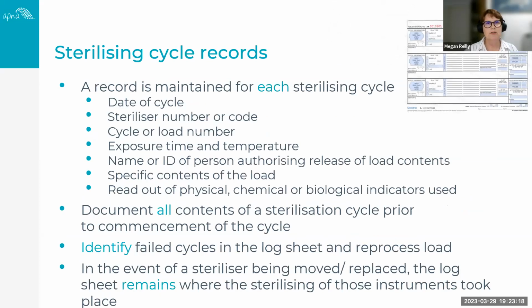So in terms of our sterilisation records, under the standard, we need to have a record for each cycle, the date of the cycle, the steriliser number, the cycle or the load number. We have to be recording the physical parameters. So that's the exposure time, the temperature and the pressure, the name of the person who's authorising the release of the load content. So this is a really critical role. We need to identify the specific contents of the load. And also the readout, as I said, of those physical parameters, but in addition, any chemical indicators or biological indicators that you may be using. So the standard requires us to document all the contents of the sterilisation cycle.